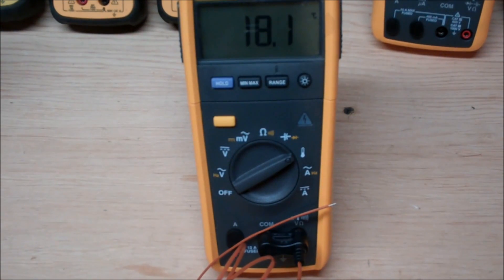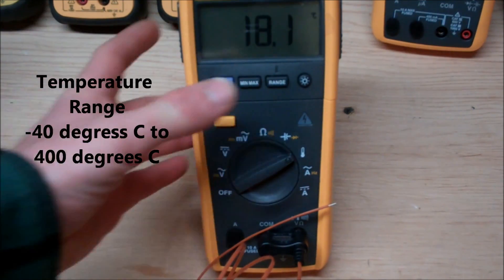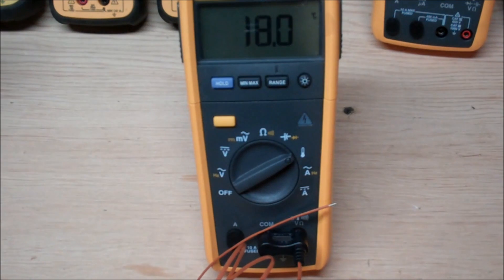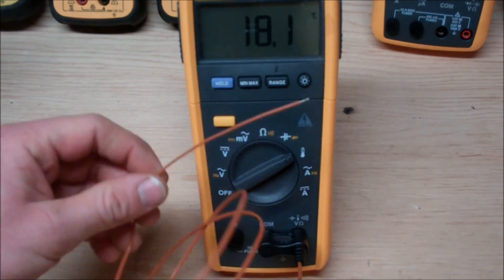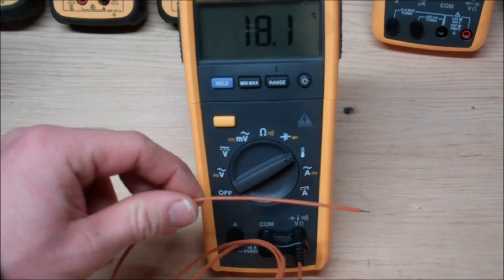Now probably one of the most useful troubleshooting tools nowadays is your actual temperature reading. And this one's really nice. It's got a diverse range from negative 40 to 400 degrees Celsius and of course that's also offered in Fahrenheit. The reason why I'm a huge fan of this type of measurement is it really does allow you to quickly analyze the situation if it's a mechanical failure or an electrical failure. If you're having a debate, if it's a mechanical failure, you hook that up to a bearing and if you see an exceeding amount of heat, you know where the problem is.